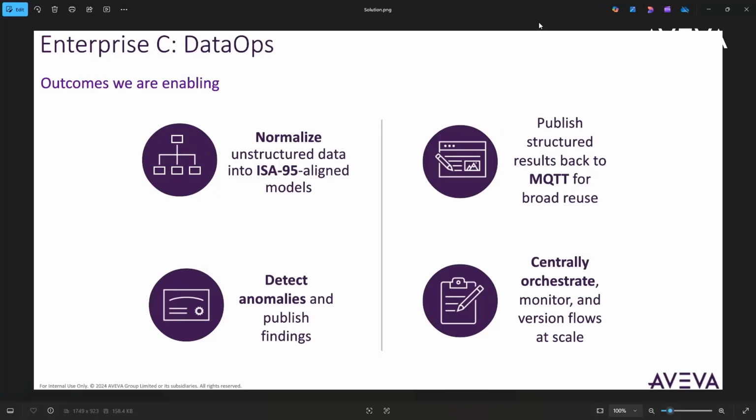And first and foremost, when we looked at the data within Enterprise C, we noticed that it was very unstructured and unorganized. Much like if you think back to the days of traditional HMI SCADA, where you have a tag that's unstructured, and then moving to a more modern SCADA infrastructure such as System Platform allows us to put the model view in place to handle structured naming conventions. So we applied the ISA naming convention to this data set. We did that using the Crosser tool. So that's value add step number one.